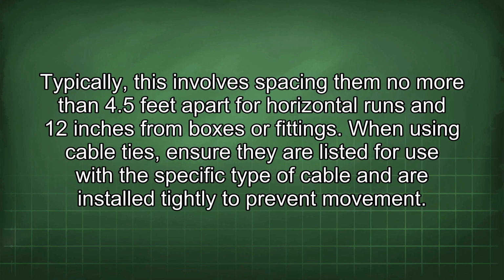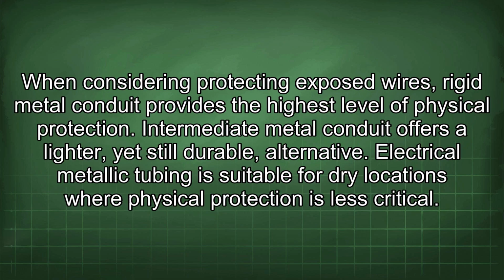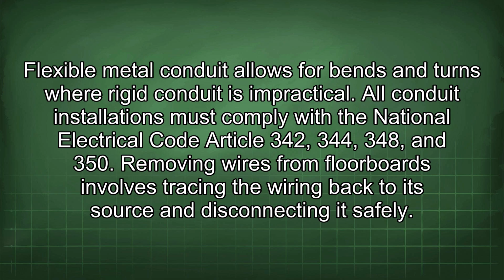Typically, this involves spacing them no more than 4.5 feet apart for horizontal runs and 12 inches from boxes or fittings. When using cable ties, ensure they are listed for use with the specific type of cable and are installed tightly to prevent movement. When considering protecting exposed wires, rigid metal conduit provides the highest level of physical protection. Intermediate metal conduit offers a lighter, yet still durable alternative. Electrical metallic tubing is suitable for dry locations where physical protection is less critical. Flexible metal conduit allows for bends and turns where rigid conduit is impractical.